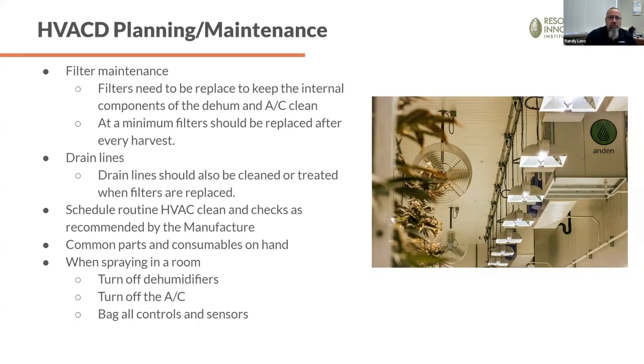Filter maintenance is something done on HVAC equipment and dehumidifiers. Filters could be looked at as a way of cleaning the air in the space, but realistically most manufacturers are looking at keeping the equipment clean. We want to keep that air conditioning coil clean, keep the dehumidifier coil clean so we don't have things growing on it and don't get reduced airflow through it because of buildup. We want to replace those filters usually after every harvest, depending on what they're doing. Some people even do it more frequently than that.